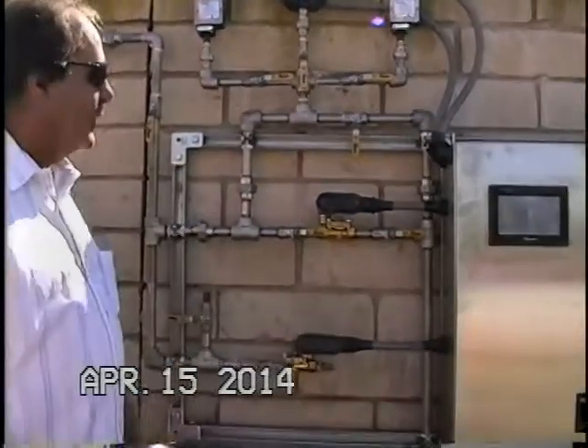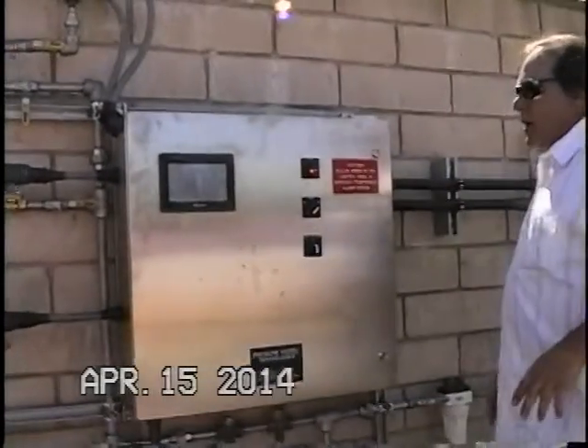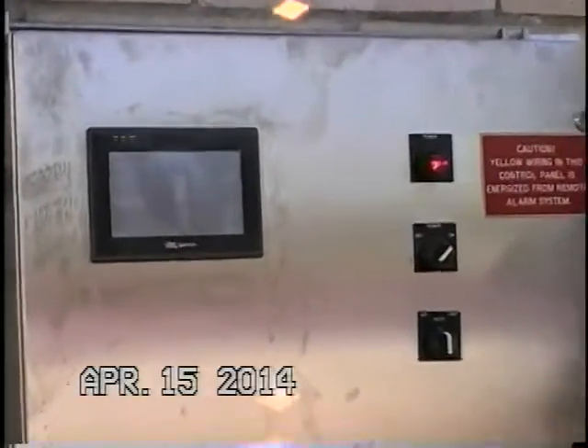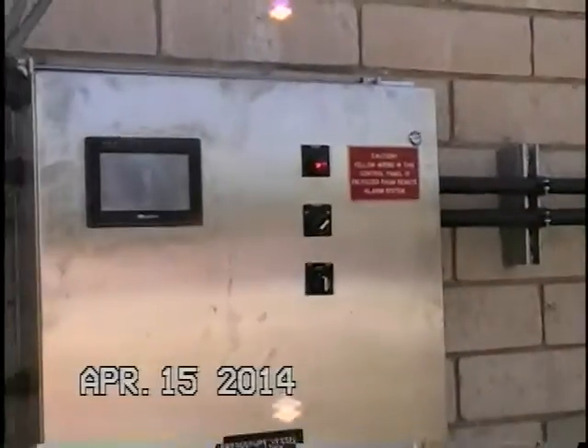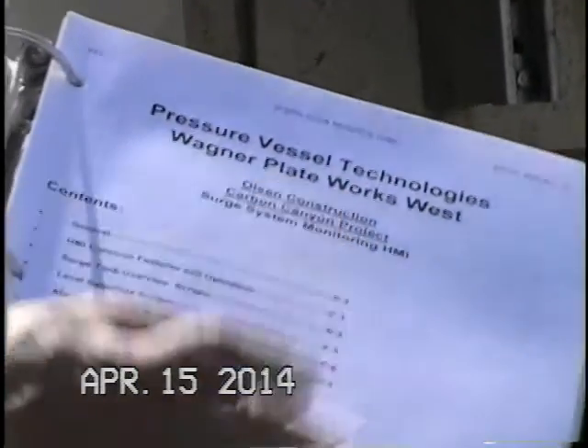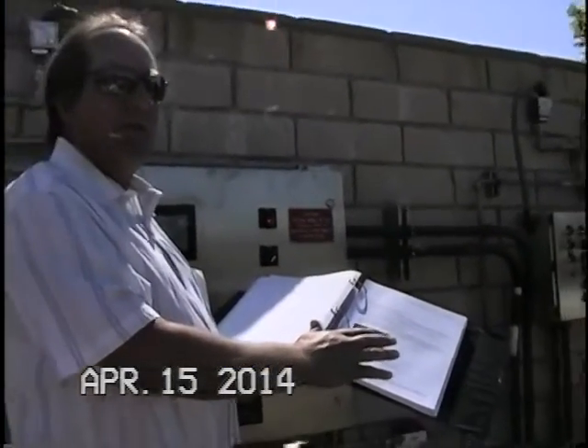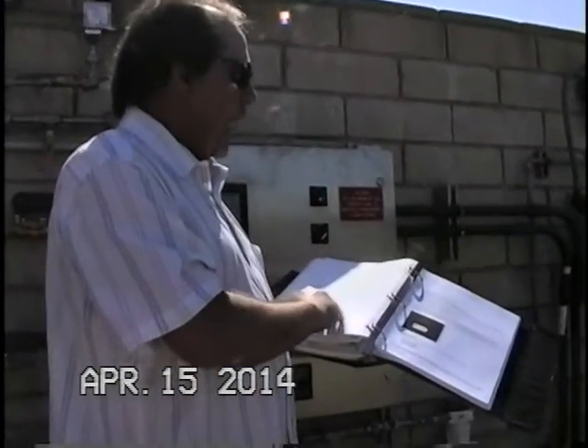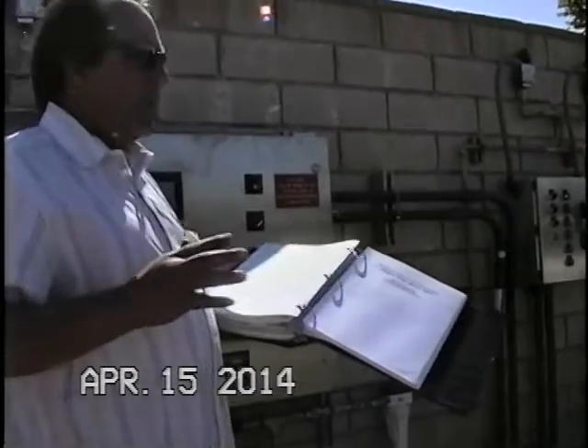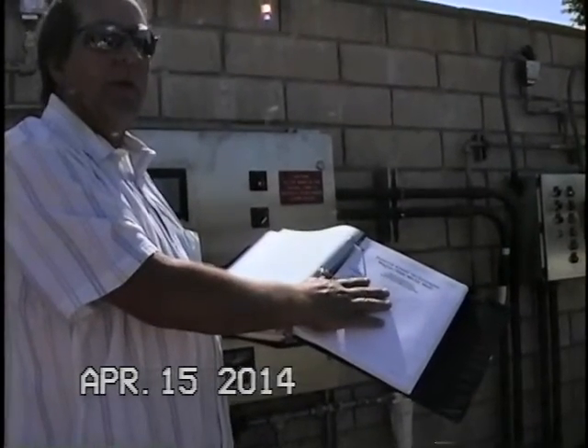No. All right, we'll go on to the most important thing. This control panel has, and within the O&M manual, we've given you a pamphlet. Bear with me just a second, let me see if I can get that. In the O&M manual, near the back, we have this Surge System Monitoring HMI section. It gives you a nice little overview of the screens, the screenshots, and how to adjust the various liquid levels within the OIT. So I would highly recommend, if you're going to be an operator that's part of this system, this is probably one of your most important documents to take a look at.